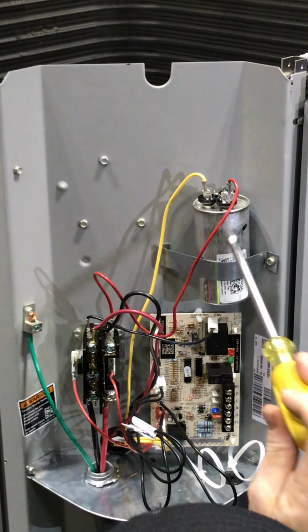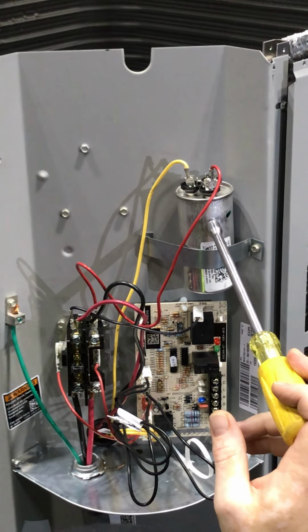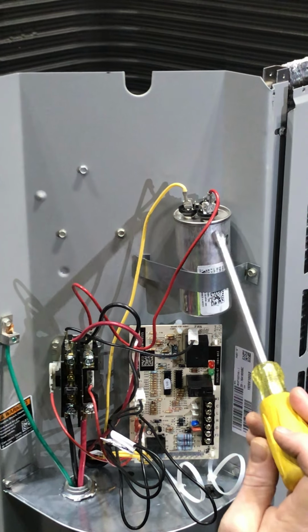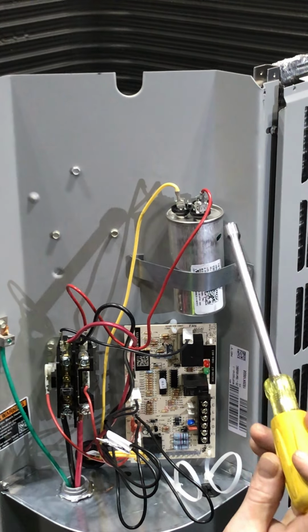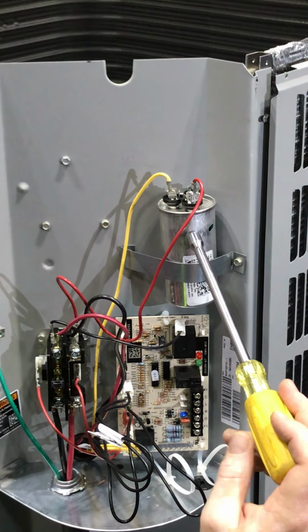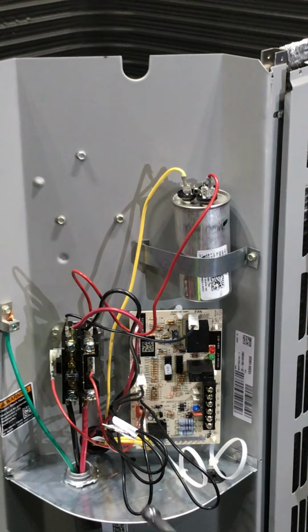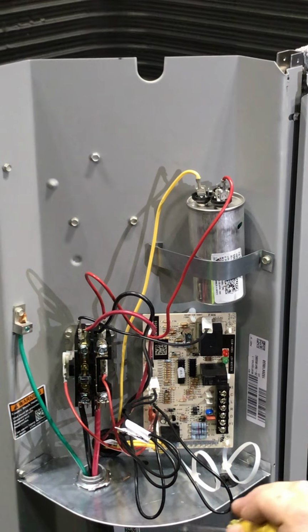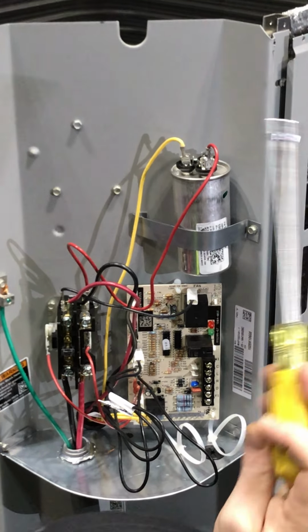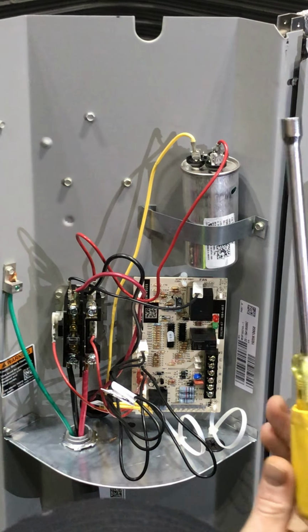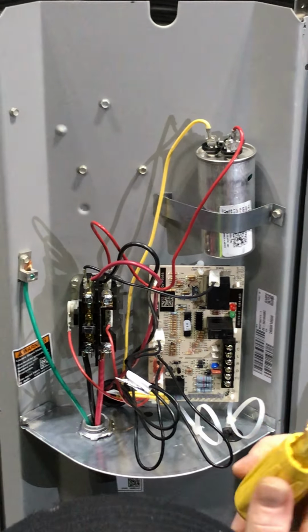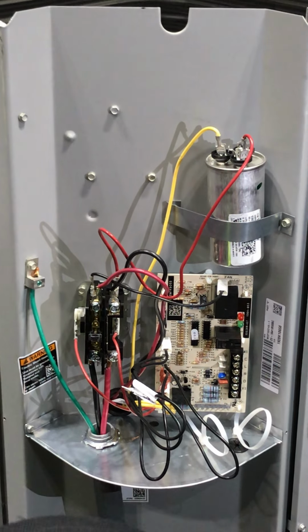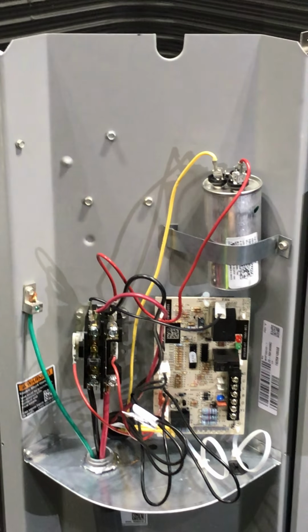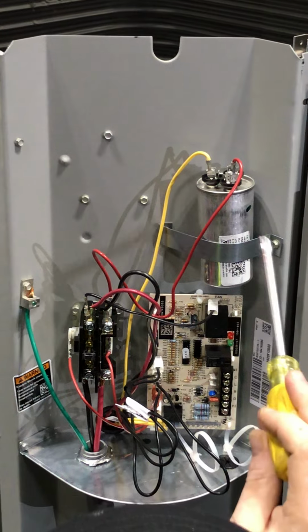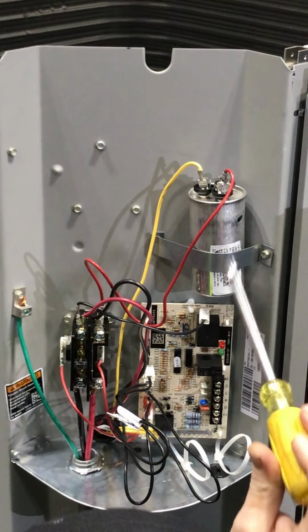Richard, what's this guy's job? What's the name of it? The capacitor. All right. So if my fan's running but my compressor's not running, check your capacitor. If your compressor's running but your fan's not running, check your capacitor. If nothing's running, I would check the contactor first and then check your capacitor. But the capacitor can go bad. Definitely after lightning storms, you'll be replacing a lot of these. A car accident that happens too close, you'll be replacing these. Too much electricity that comes through this thing will be absorbed. That's what it does. It absorbs electricity. It's like a little battery.